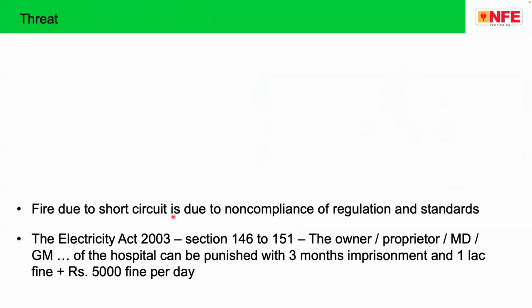Please note that fire due to short circuit is due to non-compliance of regulation and standard. It is not because a short circuit is not supposed to create fire. In case of a short circuit, much before the short circuit creates a fire, the protective device is supposed to trip the supply. Fire due to short circuit is due to non-disconnection of the supply. That means your protective devices are not efficient.